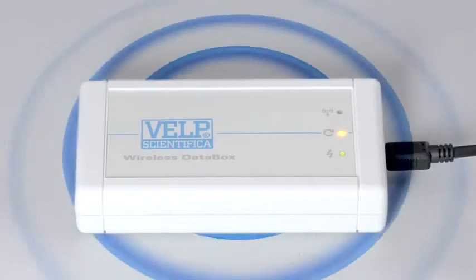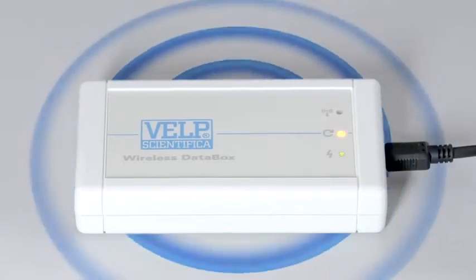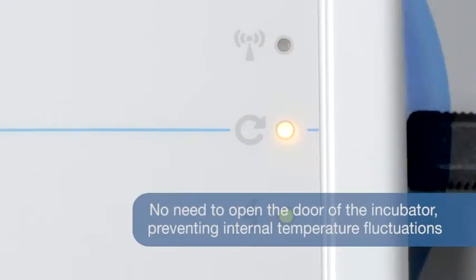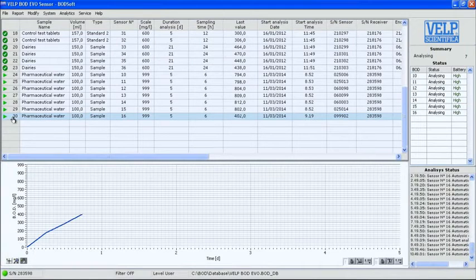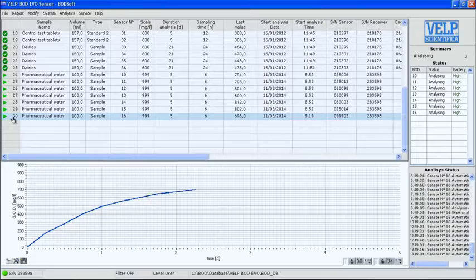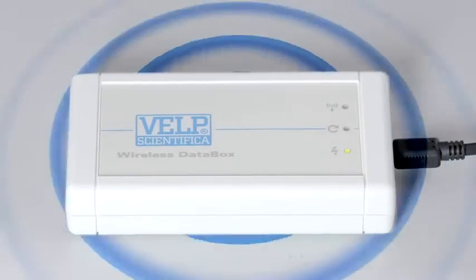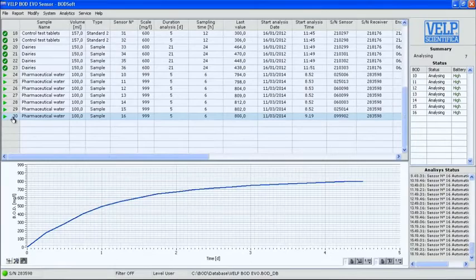BOD-EVO sensor ensures outstanding reliability as there is no need to open the door of the incubator for data monitoring. There is no risk of internal temperature variation during the test. Forget about the analysis, results will be sent automatically to the wireless data box.